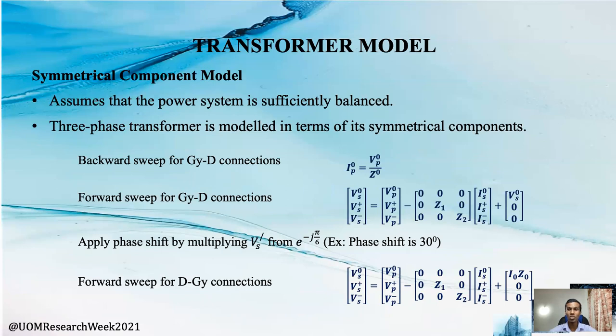For transformers, we use the symmetrical component model. The transformers are modeled using symmetrical components assuming the power system is sufficiently balanced, though according to the literature this model can be used for unbalanced scenarios as well. Both grounded Y-delta and delta-Y transformers are modeled in the algorithm for any phase shift given by the user.